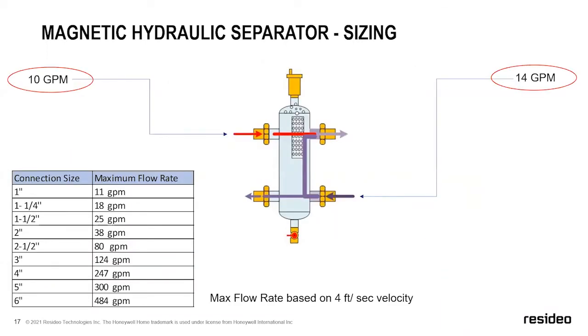One of the questions that I do get a lot is, well, what size hydraulic separator should I use? And some people overthink this a little bit. We do have some tables published that show our maximum flow rate capacities for each hydraulic separator. But really, you want to size these so you're going to have less than 4 feet per second velocity going through the hydraulic separator. When I used to design systems, we always shot for that as a maximum flow anyways, because when you start getting more than that, you'll start having velocity noise issues in the system. And then if you get much beyond that, you'll actually start having pipe erosion. So we always tried to keep the velocity below 4 feet per second, but you do have two different sides.